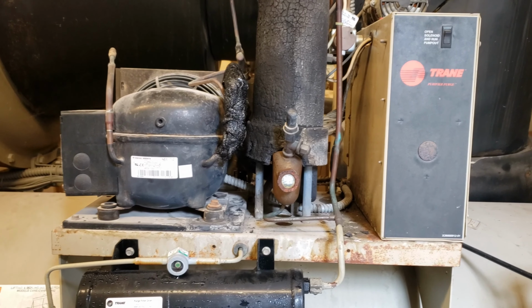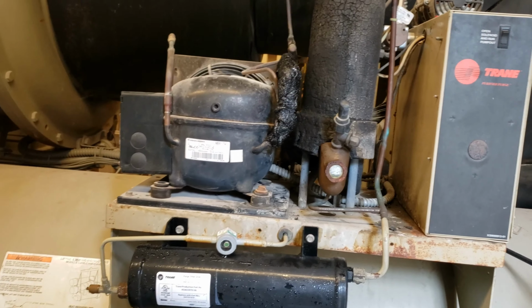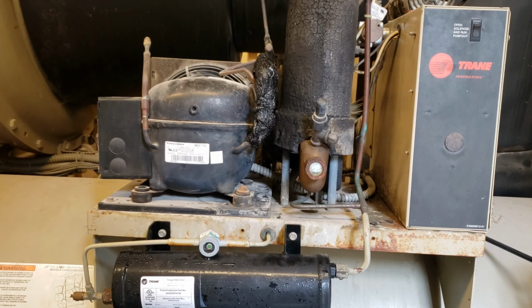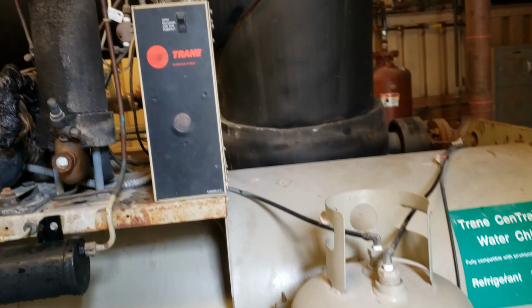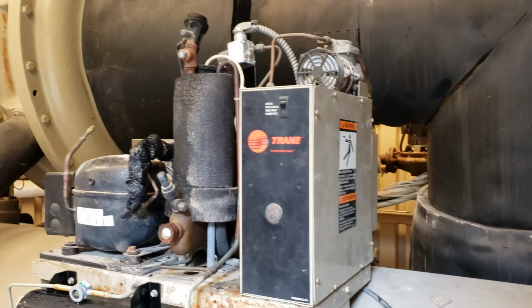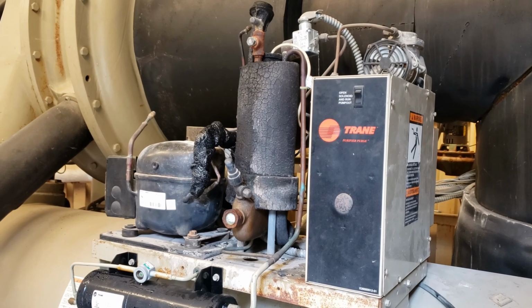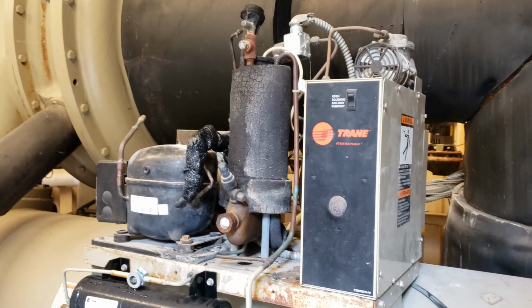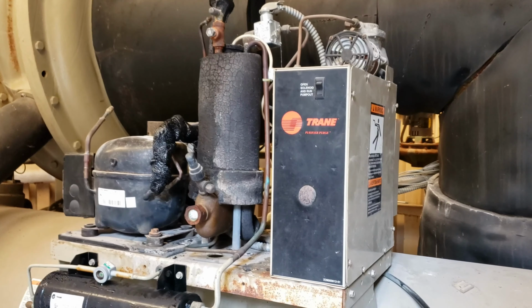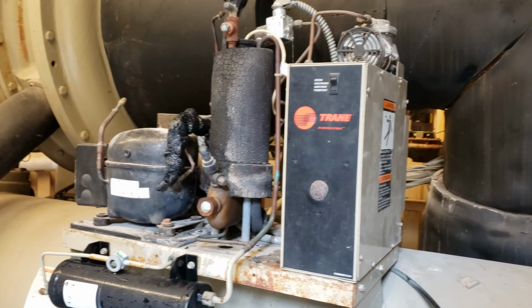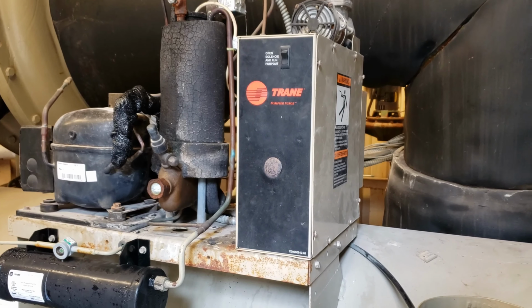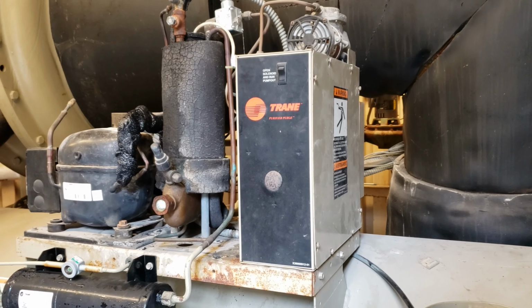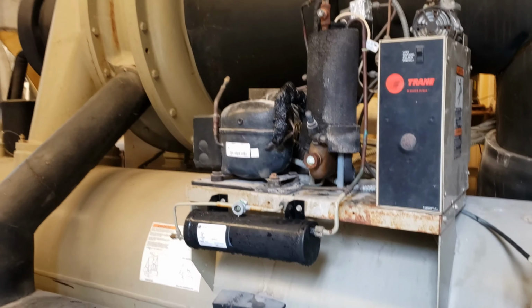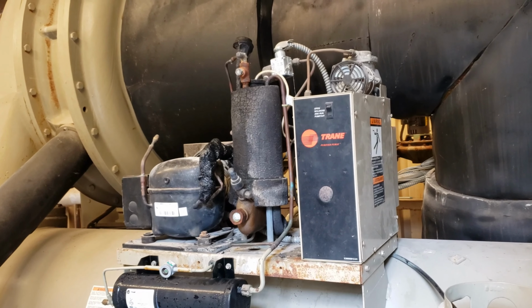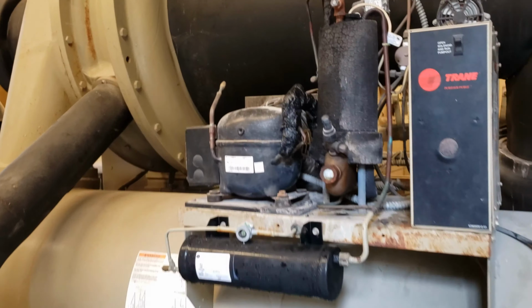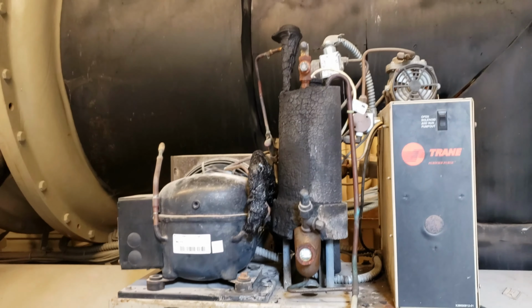And immediately upon doing that, it saw that suction temp take a dive and it started doing exactly what it needed to. And after that, it had to pump out for a solid 24 hours. It pumped out overnight and part of the next day. And by the time I came and checked it that afternoon, it hadn't needed a purge since. It's been perfectly fine. This chiller stopped all surging. I've been able to raise the full load current to 100%, and this thing's been working like a dream since.